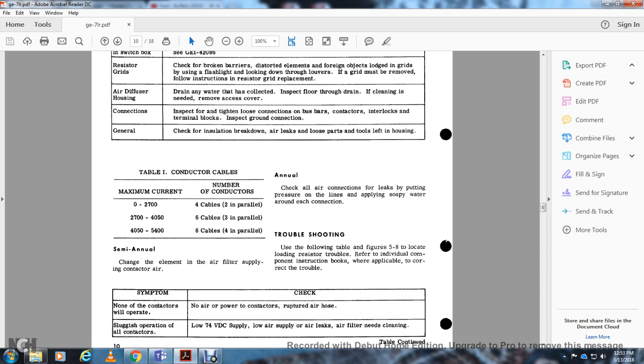Semi-annual: change the element in the air filter supply and the contactor air. Annual: check all connections for leaks by putting pressure on the lines and applying soapy water around each connection. Troubleshooting: use the following table, refer to figure 5.8 to locate the loading resistor trouble, and refer to individual components' instruction books where applicable to correct the trouble.